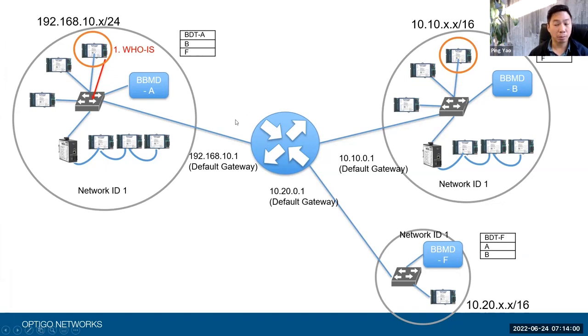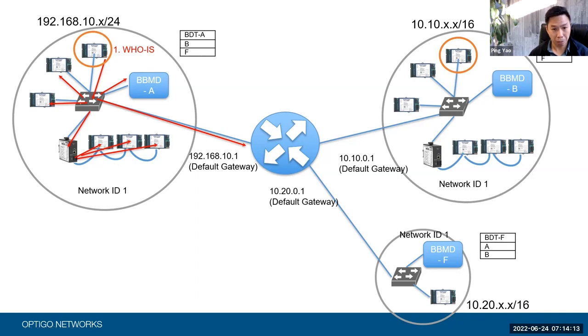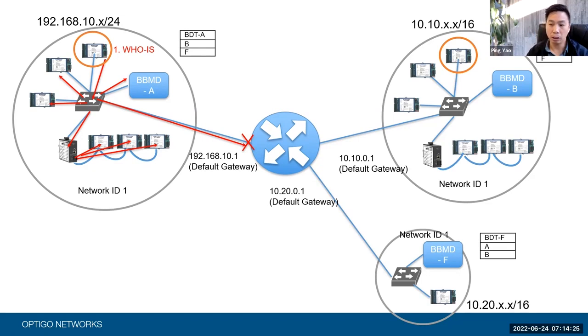If we don't have BBMDs, it's not going to work. The WhoIs will be broadcasted — and I want to reiterate here, it's going through a BACnet router. The BACnet router is still transferring the broadcast, so BACnet routers do not block BACnet broadcast. But this one will hit the IT router, the IP router, and the IP router will block it. So if we just stop there, we will never be able to discover it.